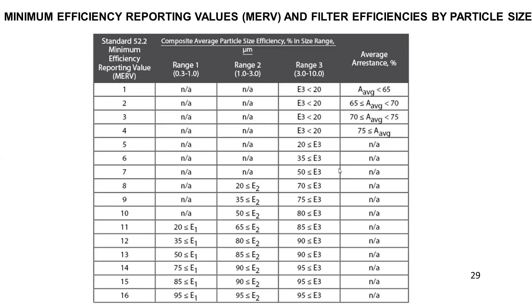Hygienic criteria for filtration in HVAC systems. Basically it is recommended to use at least 2 stages of filtration. One filter stage should be installed prior to the cooling coil. Here, this is the cooling coil, and prior to that is the pre-filter. Then, after the blower, you should have filter bank 2, the fine filter, to avoid contaminants coming from the blower.